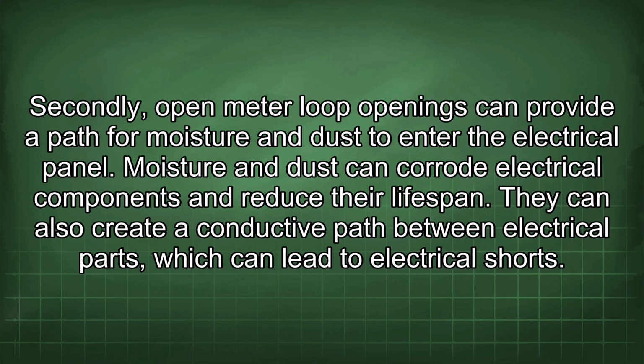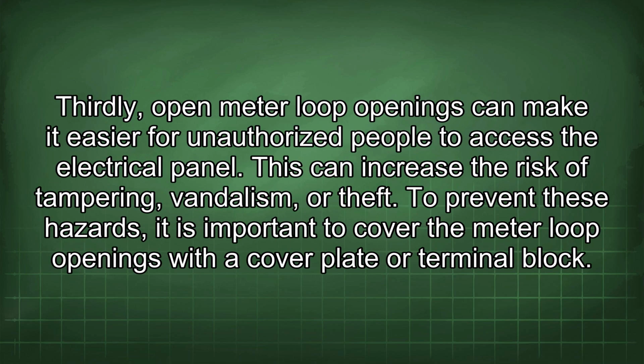Moisture and dust can corrode electrical components and reduce their lifespan. They can also create a conductive path between electrical parts, which can lead to electrical shorts. Thirdly, open meter loop openings can make it easier for unauthorized people to access the electrical panel. This can increase the risk of tampering, vandalism, or theft. To prevent these hazards, it is important to cover the meter loop openings with a cover plate or terminal block.